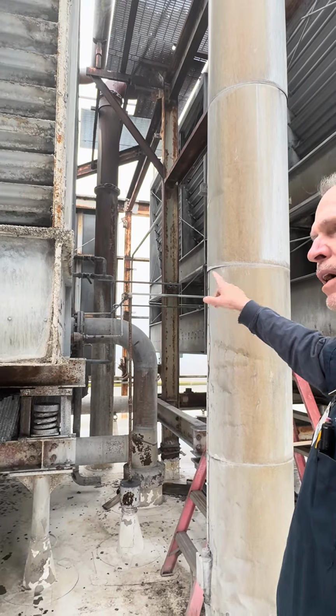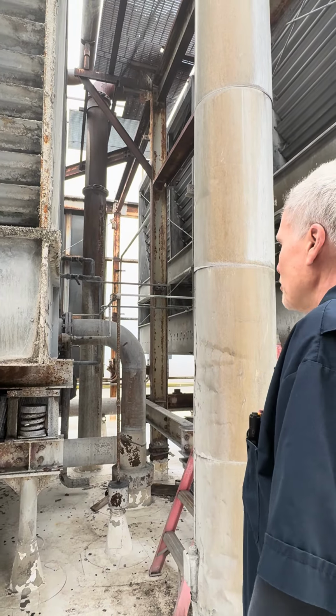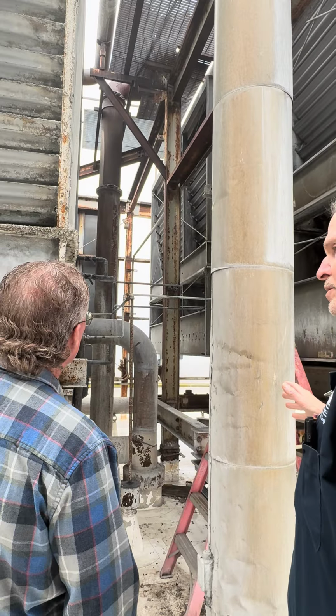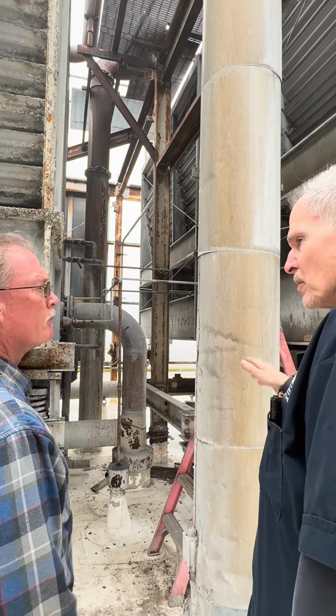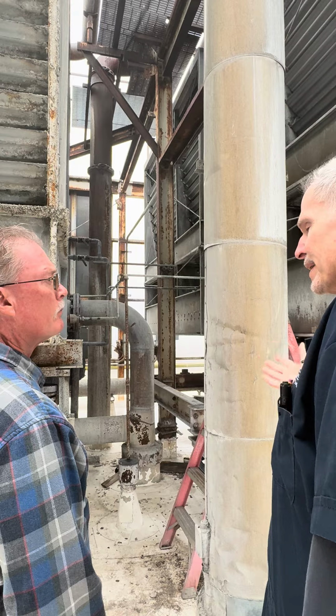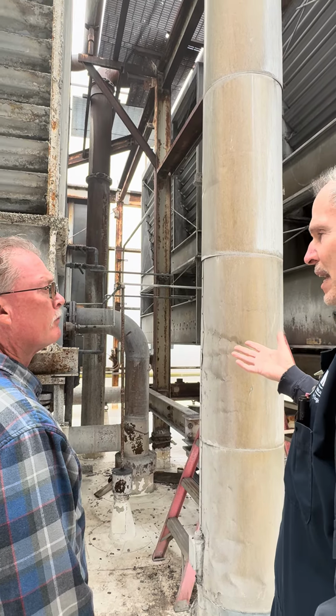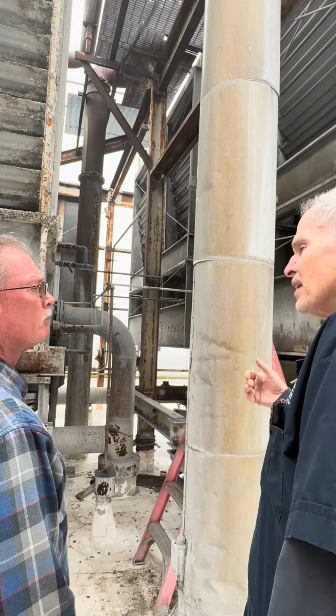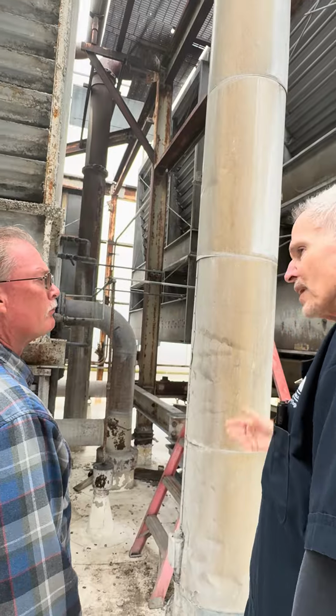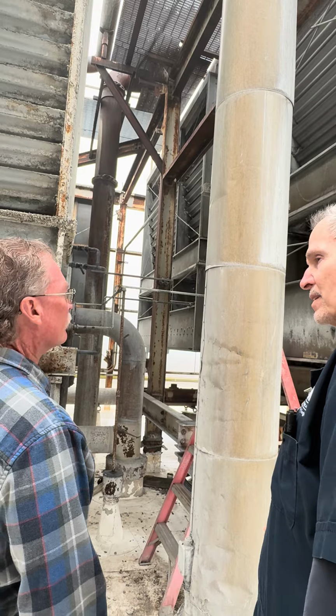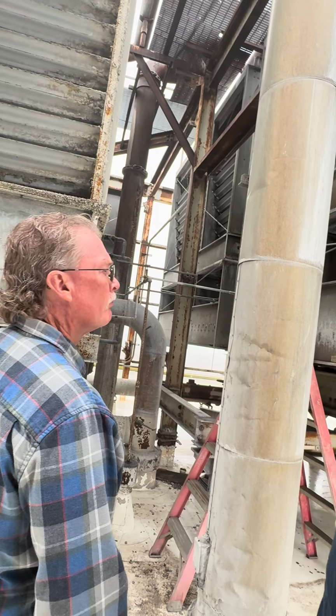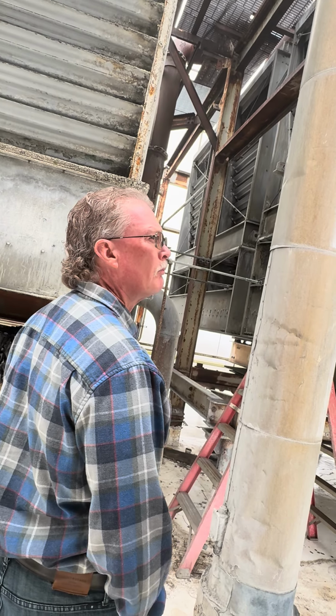I have steam coming up. Typically you want to warm it up so you don't shock the machines when starting from cold - you're bringing up 35, 40 degree water, and you don't want to run that through the condensers. Bring it up a little bit, then you're good. Early in the year, then shut them down.